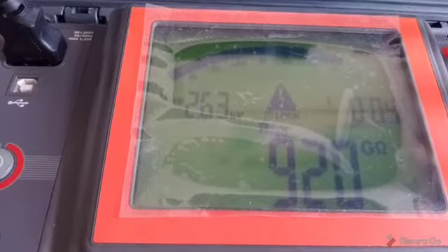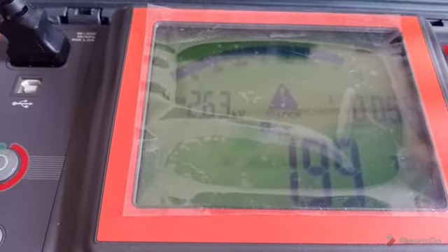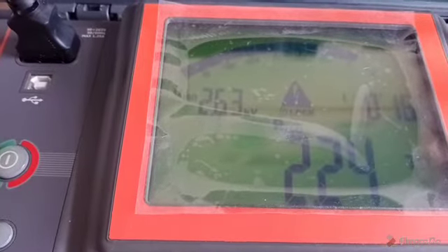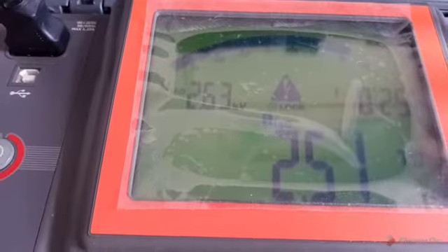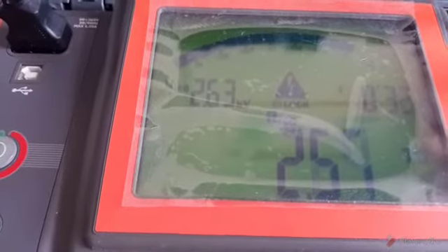Now check the insulation resistance, it is in tera ohm. T ohm is there, so you can convert this T ohm into mega ohm also. At the upper right hand side, timing is provided. 19-20 seconds are there. You have to take down the reading at 30 seconds. Now check the reading at 30 seconds, please, and note it down. So at 30 seconds, 2.48 tera ohm is there. Next reading is at 60 seconds.